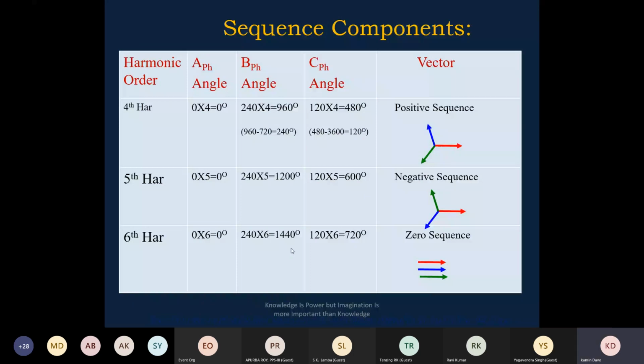The severe heating will start. Why will the severe heating start when the core is getting saturated? Because the negative sequence current will be high, the losses will be very high inside. So the severe heating starts in the transformer cores. So that is how the fifth harmonic, you look at it here. So that is why we can set the fifth harmonic also in the transformer differential relay.